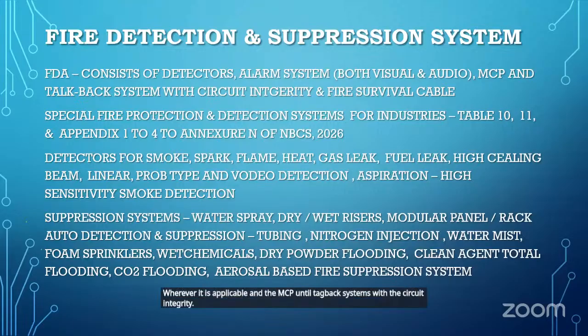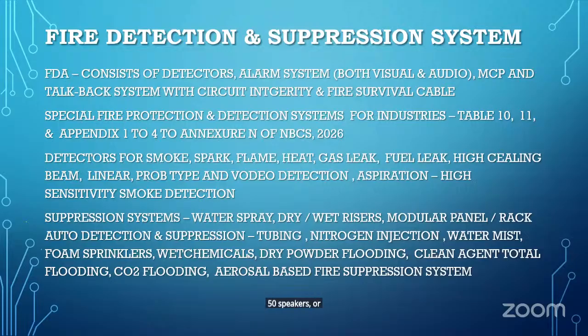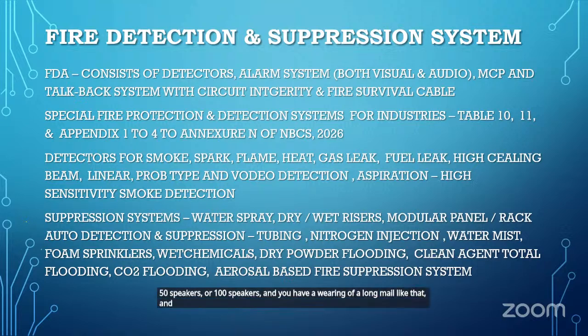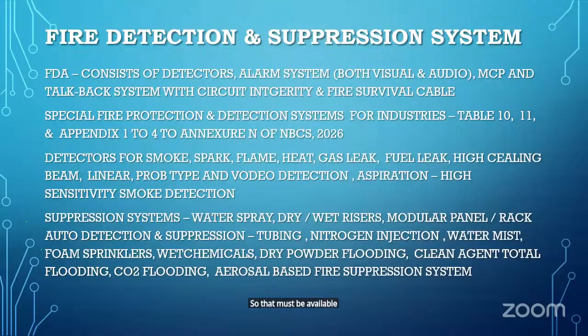So what is circuit integrity? Circuit integrity is an electrically supervised system. Say you have 300 detectors, 50 speakers or 100 speakers, and you have wiring of a long length, and there are so many connections. Anywhere any problem occurs, the circuit integrity self-supervises and communicates it to the panel. That is called circuit integrity. So that must be available as per the standard, as well as for the NFPA also.